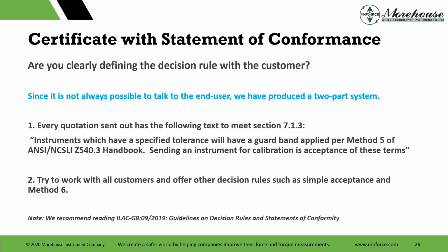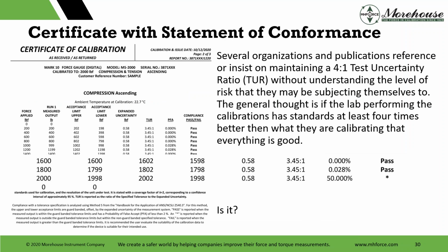And then also, we try to work with all customers and offer other decision rules such as simple acceptance and method 6. Really do not want to offer simple acceptance because I don't think that meets the intent of this standard. Though if somebody wants it, the standard's very clear that the customer can overrule, good metrological practice in this case, and say, give me a simple acceptance. And we strongly recommend for more reading ILAC G8 2019 for decision rules and statements of conformity. Also, there's method 2, there's root sum squared. There's a lot of different methods out there for guard banding that are acceptable.